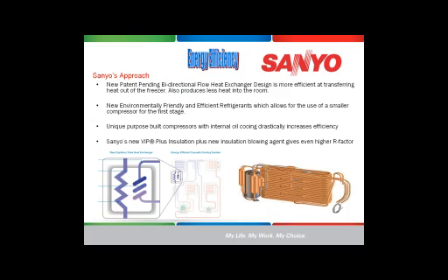Our approach in the last several years is to introduce a new patent-pending bidirectional flow heat exchanger, fancy word for how we internally in the freezer remove heat energy in areas that you don't see. This is the prime reason that our freezers perform well for energy. We also were able to introduce some new environmentally friendly refrigerants which allow us to use a smaller compressor in the first stage of the systems. If you're familiar with ultra-low freezers, you know that most of them are cascade designs and they require 2 compressors to be able to bring the freezer down to -85 or -80, depending on what your set point temperature is.